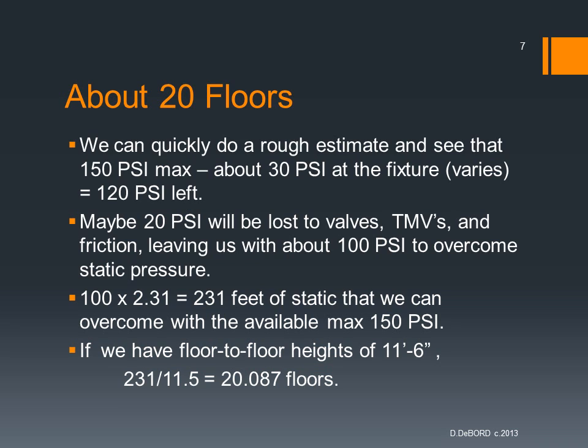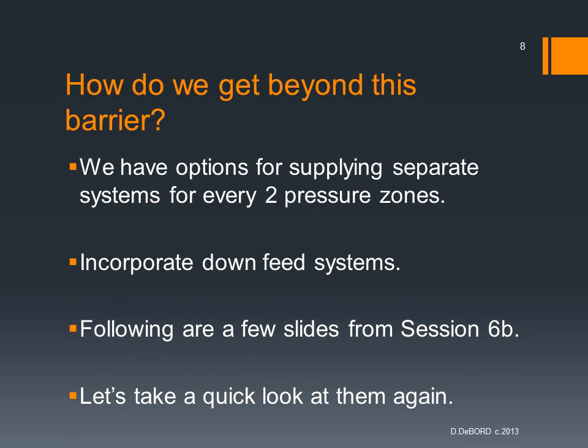So we have a floor-to-floor height, let's just say, of 11'6". 231 feet divided by 11.5 is about 20 floors. So roughly 20 floors could be covered with that 150 psi. So what do we do about that? Can we get beyond that barrier? Well, sure we can. We have some options for supplying separate zones for every 2 pressure zones. But we can also incorporate downfeed systems, and other things. And we have a few slides here that you may recall from last week, session 6B. So let's take a look at them again and go into a little more detail.